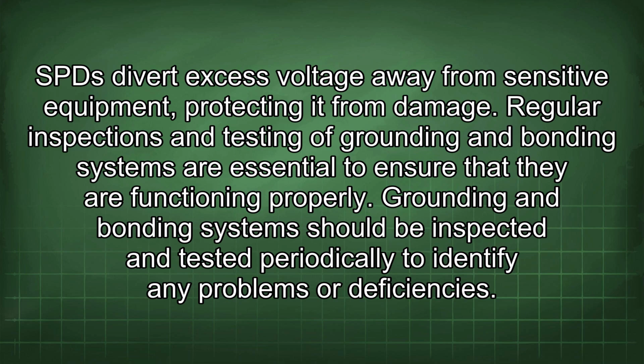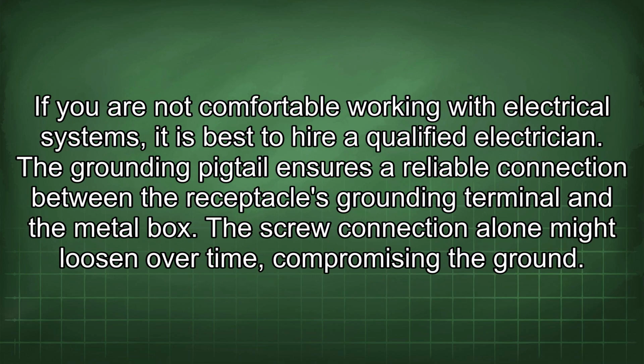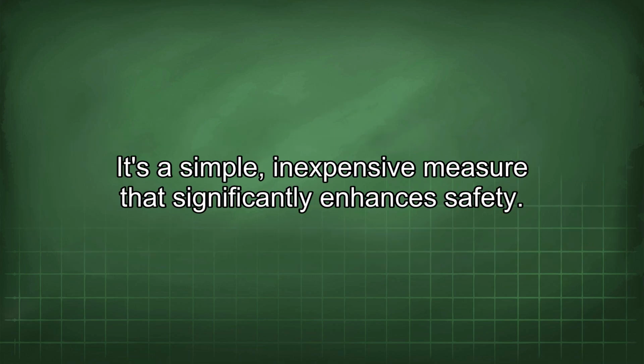Regular inspections and testing of grounding and bonding systems are essential to ensure that they are functioning properly. Grounding and bonding systems should be inspected and tested periodically to identify any problems or deficiencies. If you are not comfortable working with electrical systems, it is best to hire a qualified electrician. The grounding pigtail ensures a reliable connection between the receptacle's grounding terminal and the metal box. The screw connection alone might loosen over time, compromising the ground. It's a simple, inexpensive measure that significantly enhances safety.